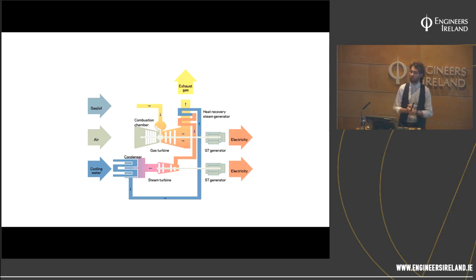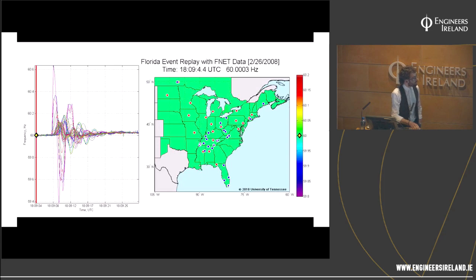Now that air is compressed, and that compressor has a speed which is linked to the frequency. So if the frequency is rising because of this short circuit fault, all of a sudden the compressor speeds up and we have more air coming in. So all of a sudden we're getting leaner. Now what controls the gas flow? That's the governor. So if the frequency rises, the governor is going to respond to that and pull back the fuel. So all of a sudden we're getting leaner again. And if that gets too extreme, you can have a lean blowout, and the gas turbine will trip off as a result. So as an illustration of that, what I'm going to show you is an event in Florida.